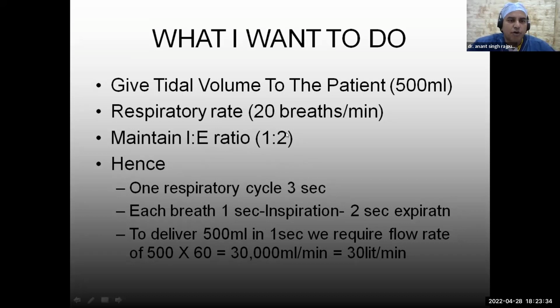Now with an I:E ratio of 1:2, is the pointer working for everyone? Yes. Okay, so in a 3 second cycle with an I:E ratio of 1:2, we get an inspiratory time of 1 second practically. Only 1 second to deliver 500 ml. So let us multiply 500 ml with this, and what figure do you get? You get a flow rate of 30 liters per minute that we have to achieve during that 1 second.